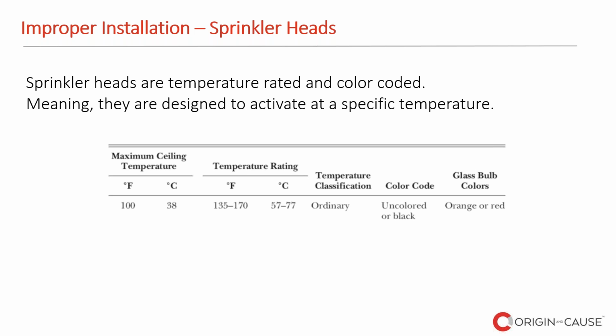As a matter of fact, I've had a number of cases like that, 3 or 4 cases, and all of them had some changes to the occupancy. So they had a small kitchen before in that commercial space, and they made a bigger kitchen. Obviously, they've done all the work, all the inspections, all the permits, but along the way, someone forgot to change the sprinkler head, and they left the lower temperature rating heads, which activated with the heat. And again, whenever you see the sprinkler heads in your office or in your building, they have color coding. If you see orange or red, those are typically for commercial or residential applications, and then they change as they go to higher temperature.